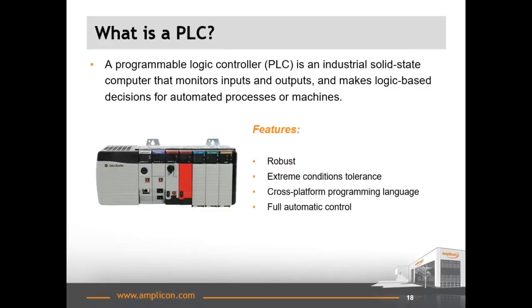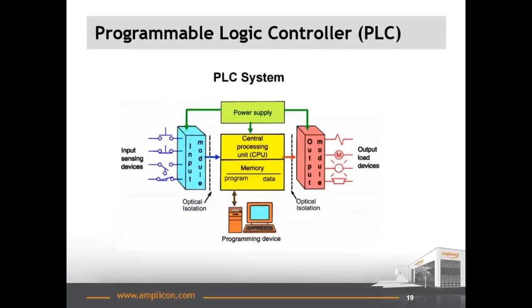Each process would normally be controlled by an individual programmable logic controller — a PLC. A PLC is an industrial solid-state computer that monitors inputs and outputs and makes logic-based decisions for an automated process or machine. They are robust and can survive in harsh conditions, including severe temperature ranges from minus 40 to plus 70 degrees and extreme moisture using PCB conformal coating. They use a cross-platform programming language, meaning regardless of the manufacturer they can be programmed without much difficulty. PLCs do have disadvantages — they do not perform well when handling complex data written in C++ or Visual Basic. PLCs can read signals from different sensors and input devices like switches, timers, and positioners, with inputs in either digital or analog form. Outputs can control external devices such as motors and solenoid valves, also in digital or analog form.